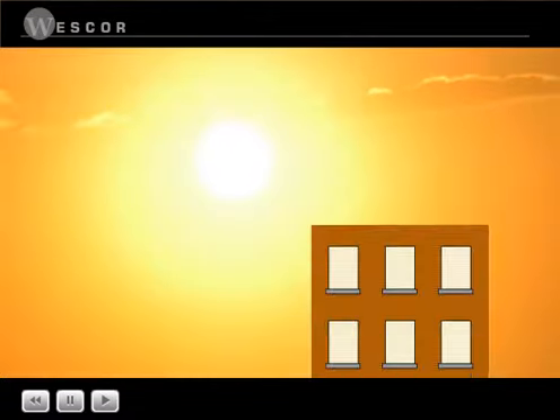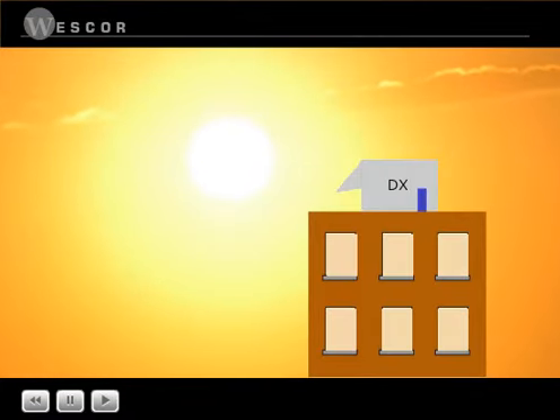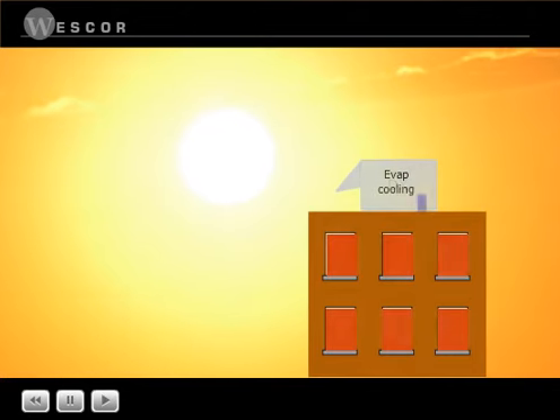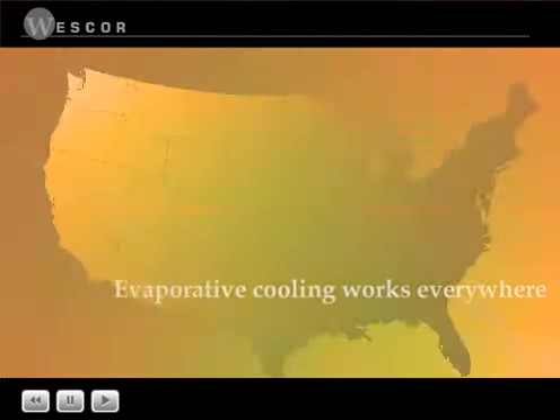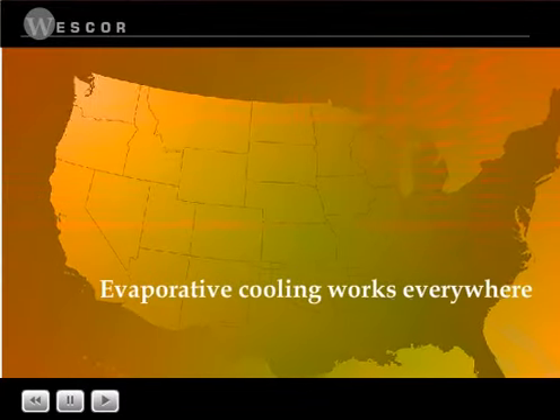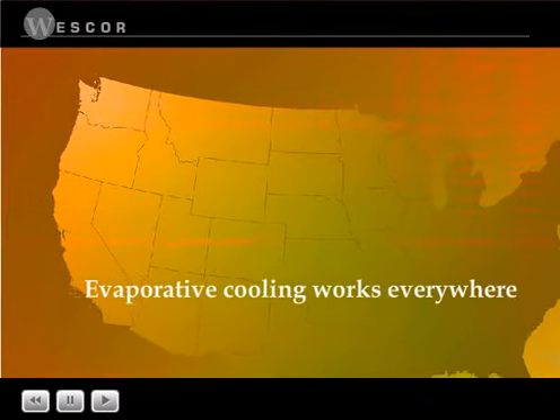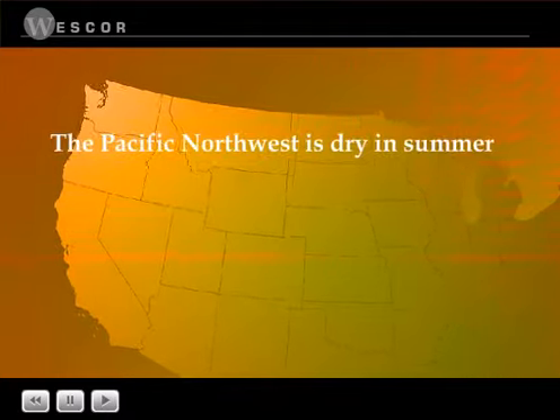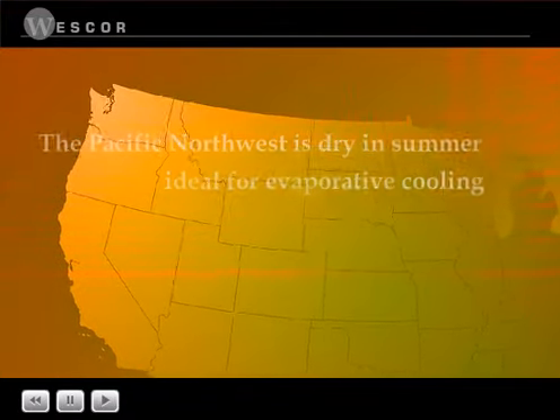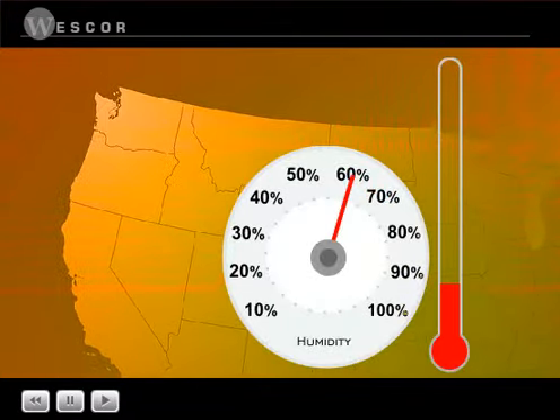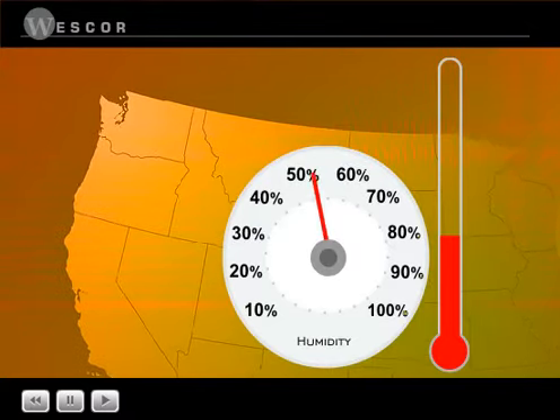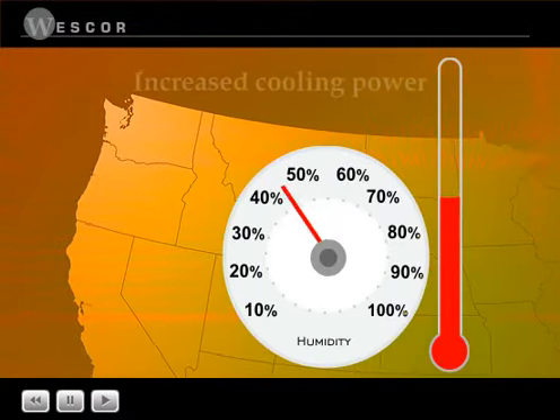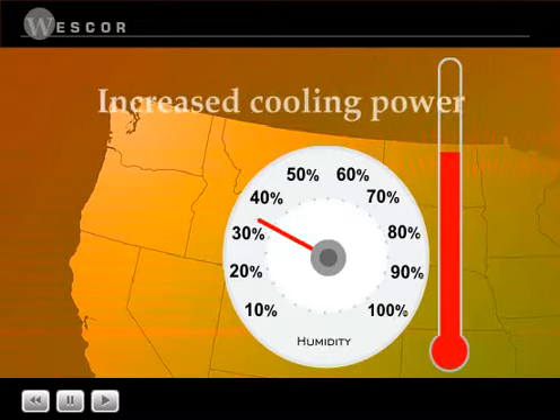The paradox of traditional air conditioning is that the hotter it gets, the less effective it becomes, just when you need cooling the most. Evaporative cooling, on the other hand, becomes more effective as the temperature rises. Evaporative cooling works in all areas of the country, not just in hot, dry climates. Although damp in winter, the Pacific Northwest is dry in summer. Humidity in this region almost always decreases as the temperature increases, and so the cooling power of evaporative systems increases.